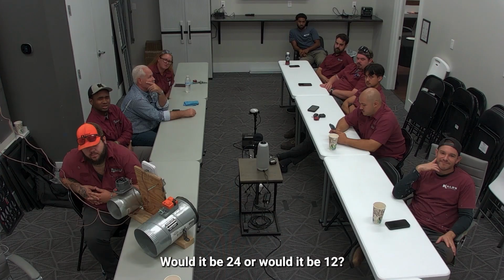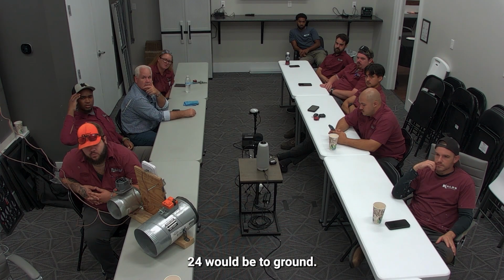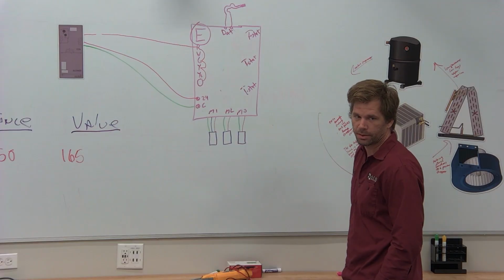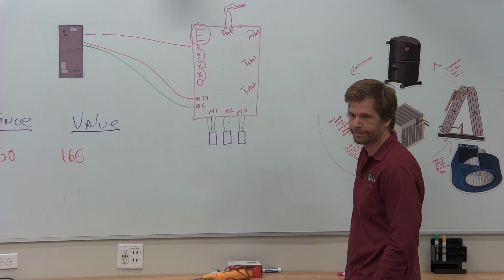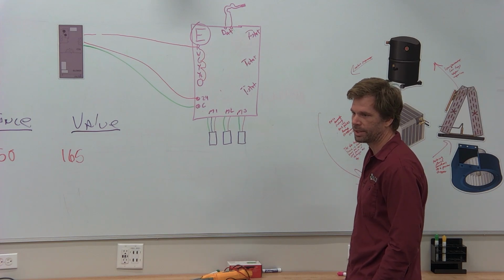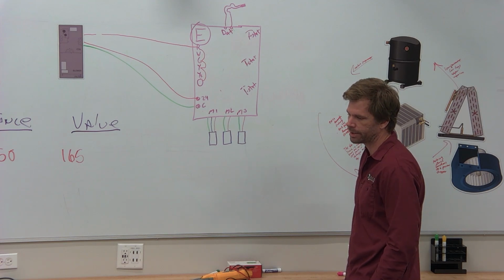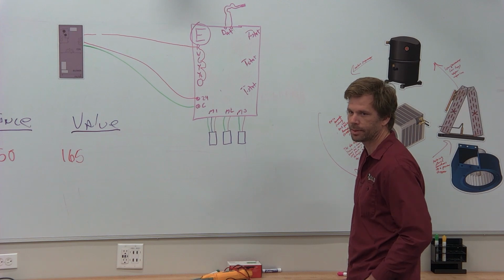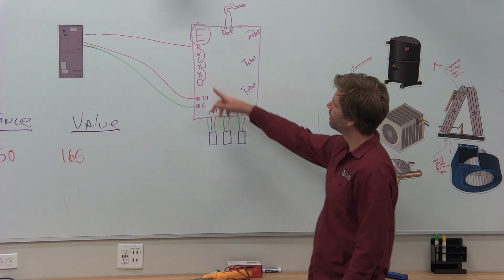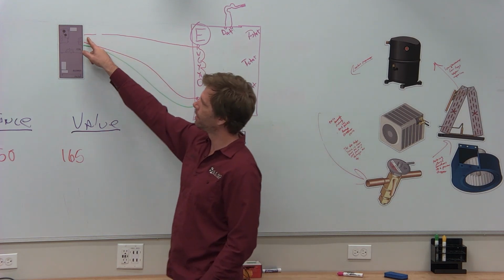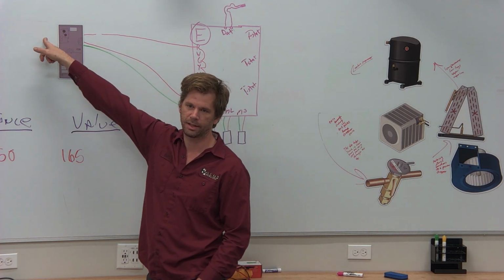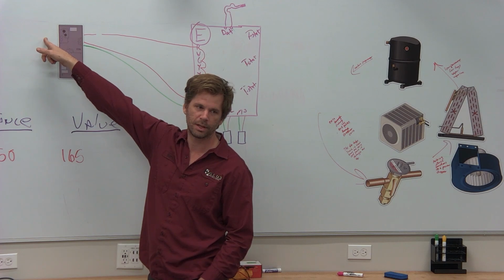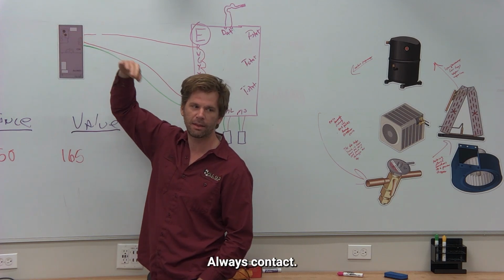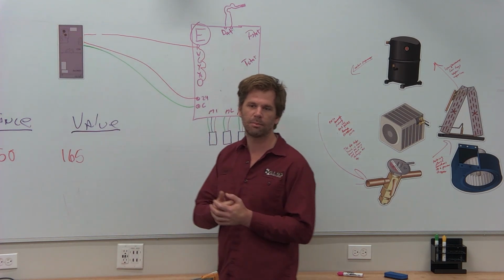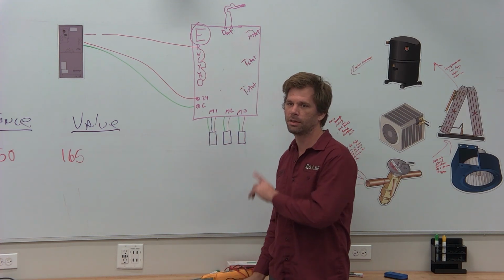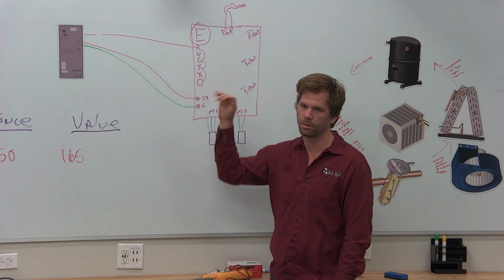Would it be 24 or would it be 12? 12, yeah. 24 would be the ground. But it'll typically show you 24. Remarkably so. Yes. I don't pretend to understand it. Actually, I do know exactly why, but I'm going to keep it to myself. The reason is because W is tied into a relay, and the relay is tied into common on the opposite side of that. And so that common didn't have to be energized. It's still a path through there. The relay's not pulling in because there's no flow, but you still have a path all the way through the relay to common.